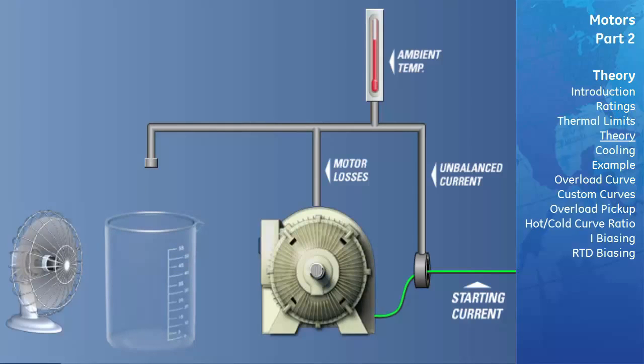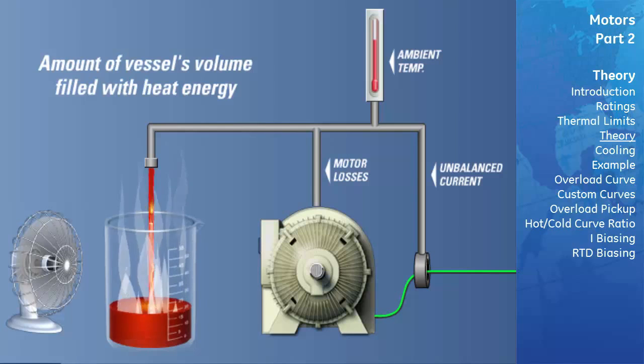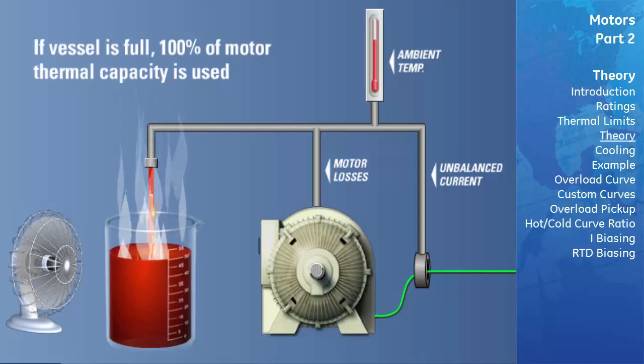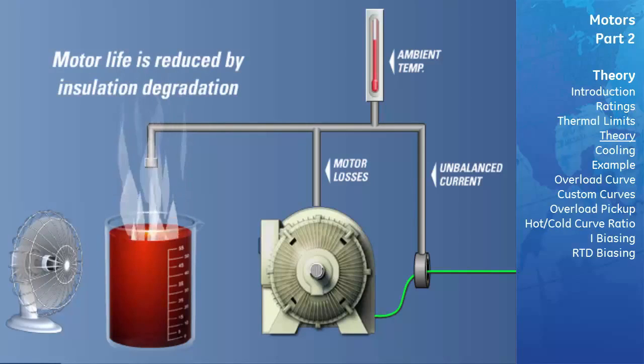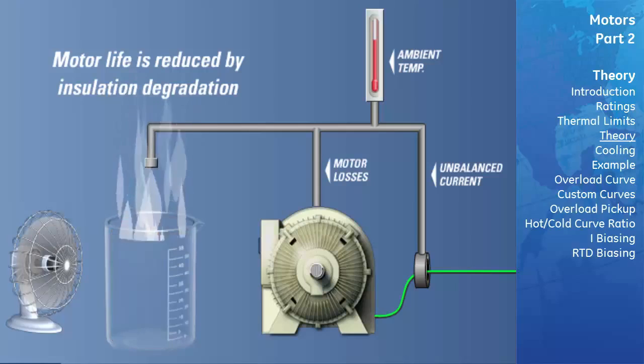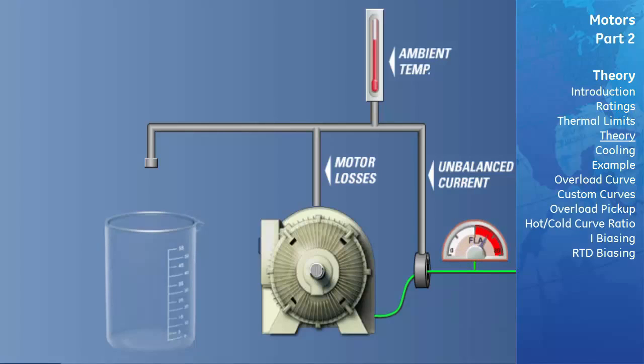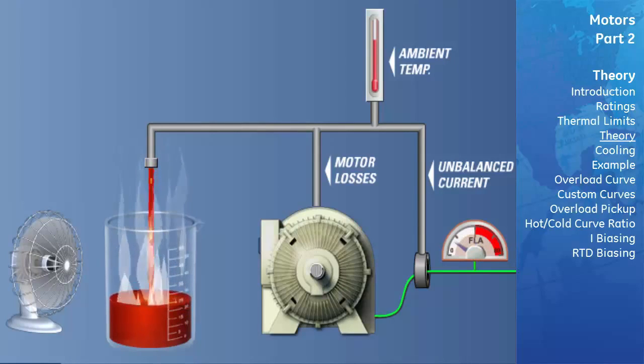The thermal capacity used is expressed as a percentage of the total thermal capacity of the motor — the amount of the vessel's volume filled with heat energy. If this imaginary vessel is full, 100% of the thermal capacity has been reached and any further increase will result in damage to the motor's insulation. The motor insulation does not immediately melt; rather, the rate of insulation degradation has reached a point where motor life will be significantly reduced. Ambient temperature and I-squared T heating start to fill the vessel when motor current is above the motor's full load current. Once motor current drops to or below full load current rating, the thermal capacity used starts to drop, as if the thermal energy is slowly evaporating from the vessel.